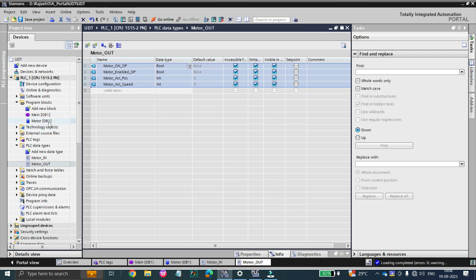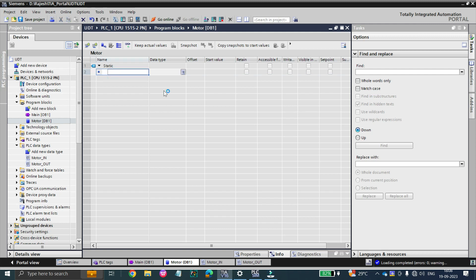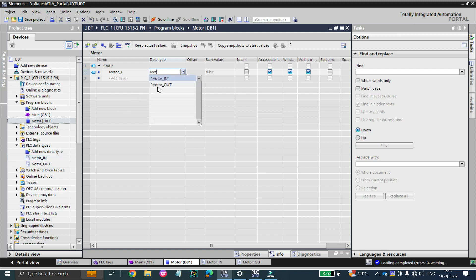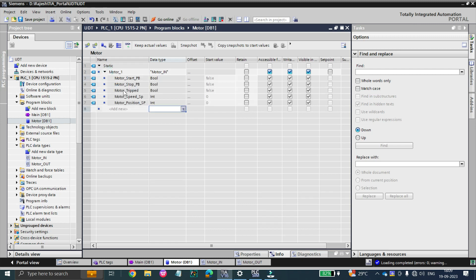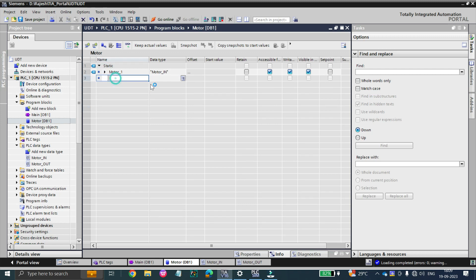Now let's see how to call motor_in and motor_out. In the static section, for motor one — instead of giving a data type of boolean — just type the name of your data type. Type 'motor_in' and the pop-up will appear. Now the data type is motor_in, and you can see an expand arrow is automatically generated. By expanding it you will find all the input tags like motor start push button, motor stop push button, and so on.